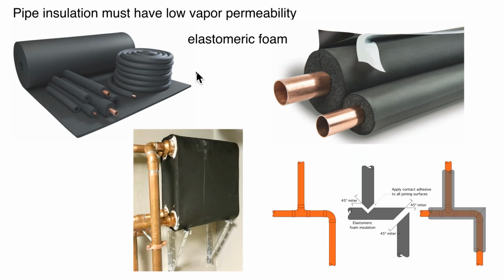Over in the lower right there, I'd like to see neatly installed insulation, and to do that, it takes a little time to cut the miter joints and glue it together properly. You don't want to leave the joints just butted together. Over time, it will shrink and pull apart, and you'll get condensation forming.